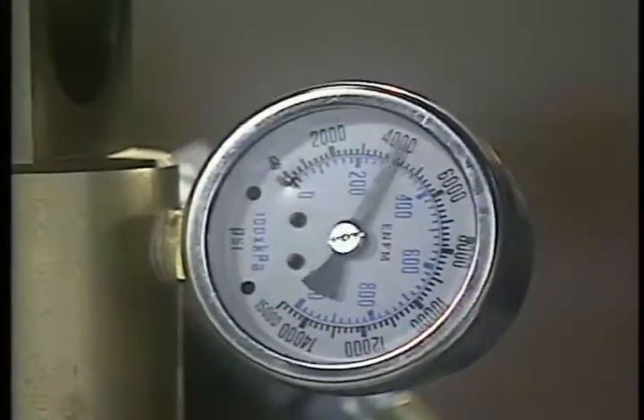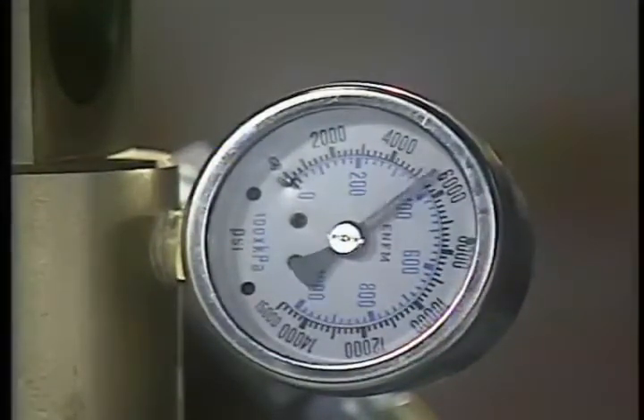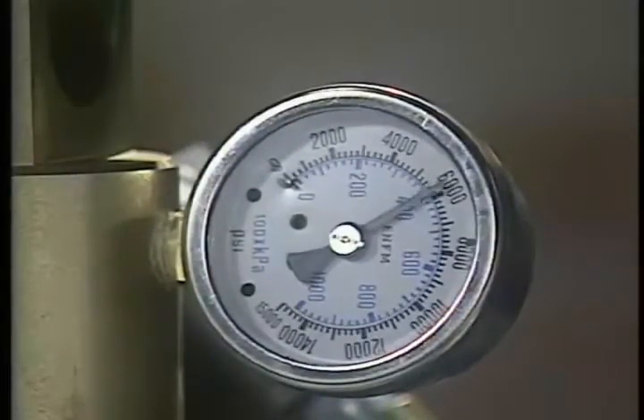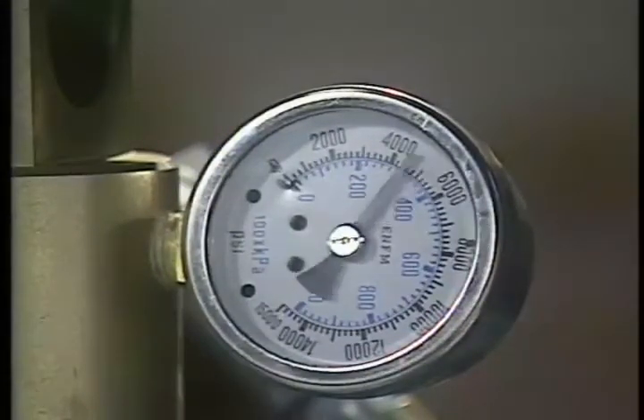When the valve sealant chamber has filled with sealant, an additional rise in pressure from this plateau will occur until the plug is finally moved off its seat. At this point, which varies from valve to valve, the gauge needle will begin to fall back. This signals that the valve is full of sealant and the plug has been moved off the taper, as per Pascal's law.